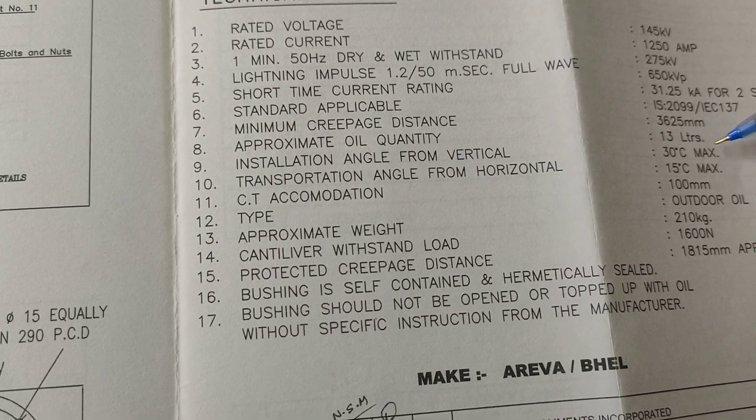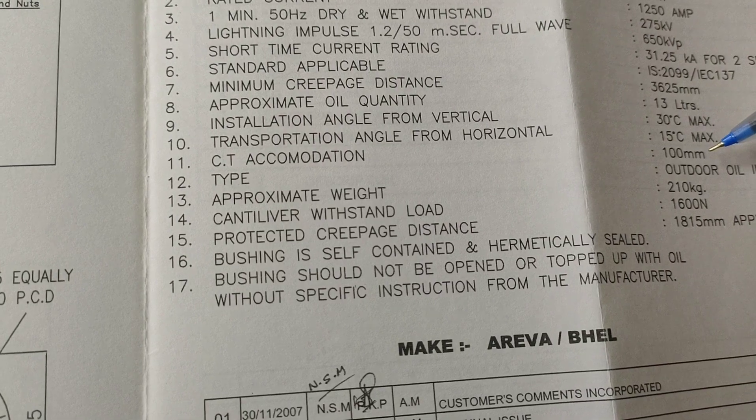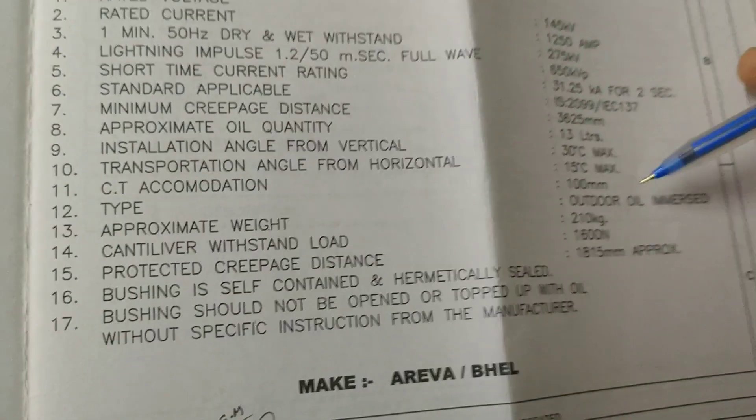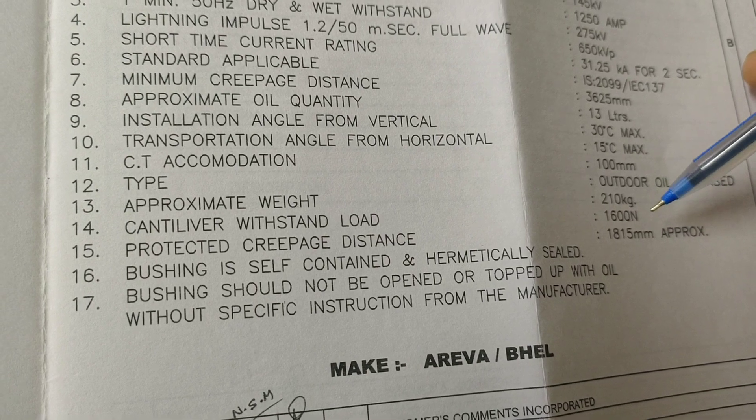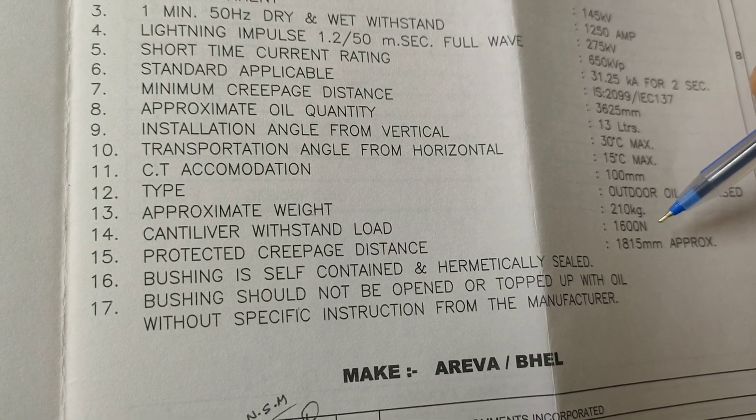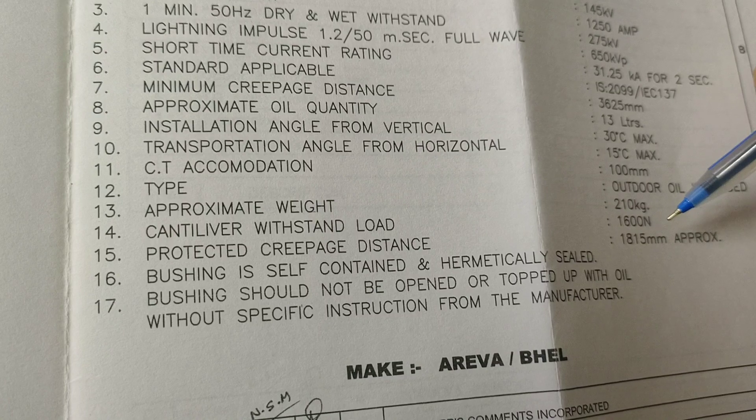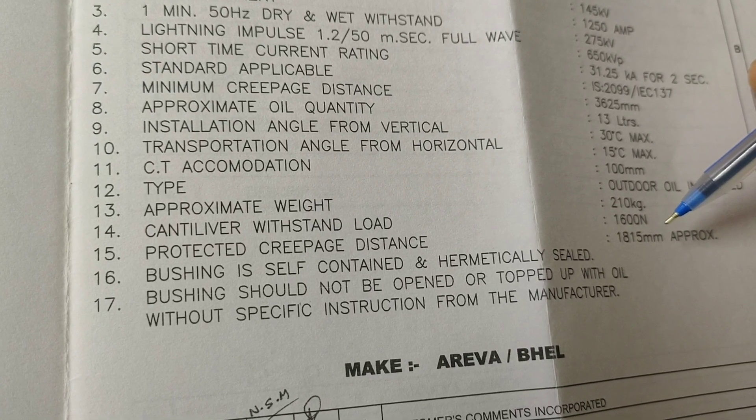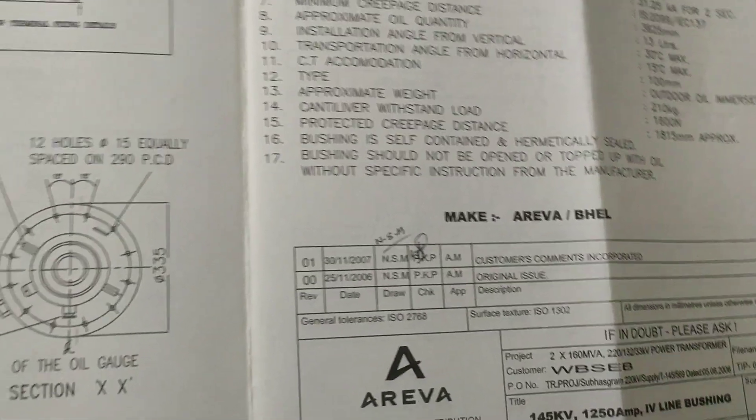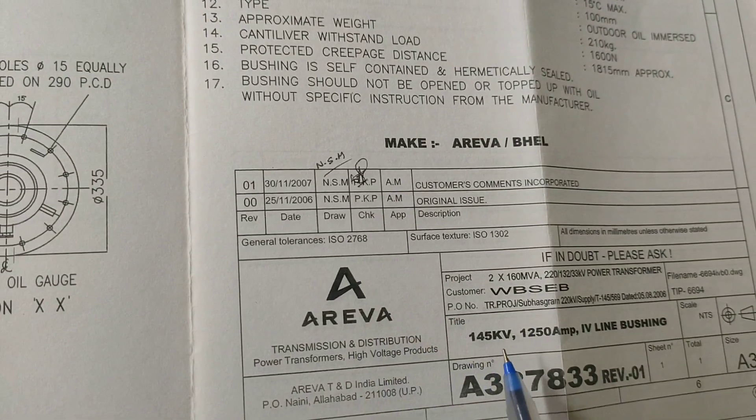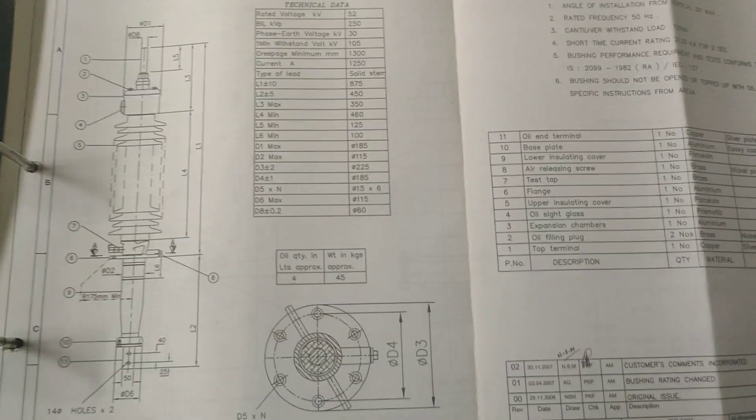Insulation angle from vertical 30 degrees, transportation angle from horizontal 15 degrees. C.T. accommodation 100 mm outdoor oil immersed, total weight is 210 kg. And also the bushing is self-contained and hermetically sealed, and the creepage protected. Creepage distance is 1815 mm approximately. So this is the 145 kV, 1250 ampere HV line bushing.